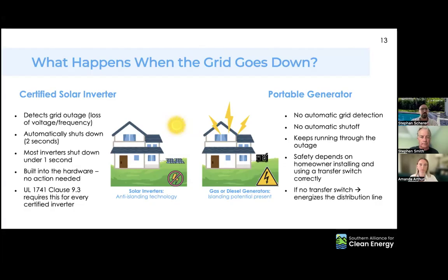Those are fairly old numbers. The industry standard now is that all these inverters shut down in less than a second, simply because it's been required in other countries in Europe. We adapted automatically -- we knew this was coming to the United States too. So inverters are shutting down in 500 milliseconds, or even 200 milliseconds. It kind of depends.